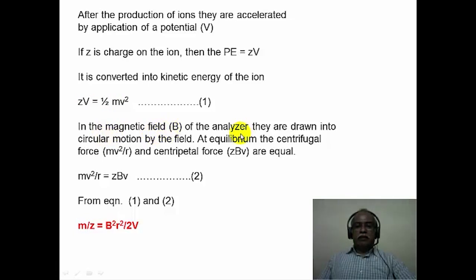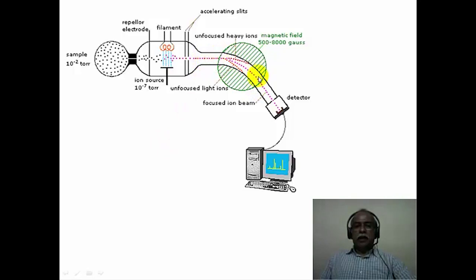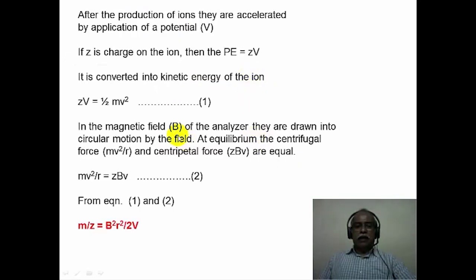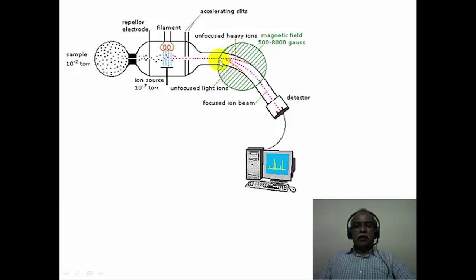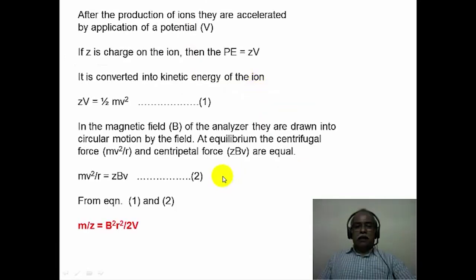In the magnetic field of the analyzer, ions are drawn into a circular motion — they take a curvature whose radius depends on the mass-to-charge ratio of the ion. At equilibrium, the centrifugal force and the centripetal forces acting on the ion are equal. The centrifugal force is mv²/r, where r is the radius of curvature, and the centripetal force is ZBv — the charge times the magnetic field strength times the velocity of the ion. When these two forces match, they are equal as represented in equation 2.